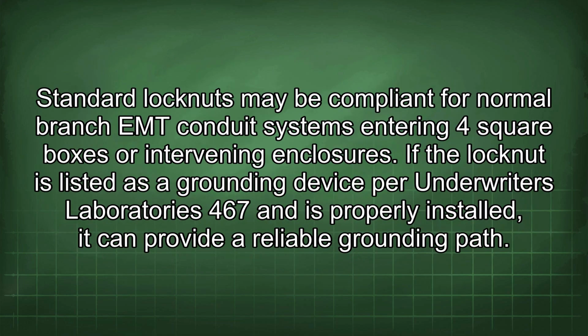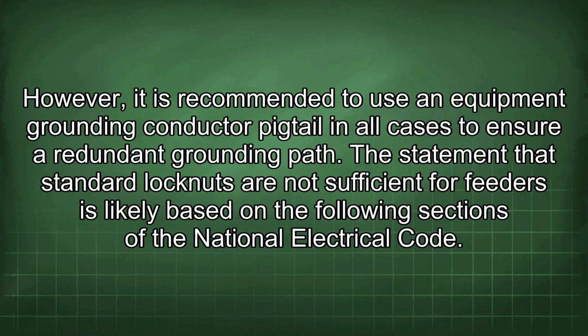Standard locknuts may be compliant for normal branch EMT conduit systems entering 4 square boxes or intervening enclosures. If the locknut is listed as a grounding device per Underwriters Laboratories 467 and is properly installed, it can provide a reliable grounding path. However, it is recommended to use an equipment grounding conductor pigtail in all cases to ensure a redundant grounding path. The statement that standard locknuts are not sufficient for feeders is likely based on the following sections of the National Electrical Code.